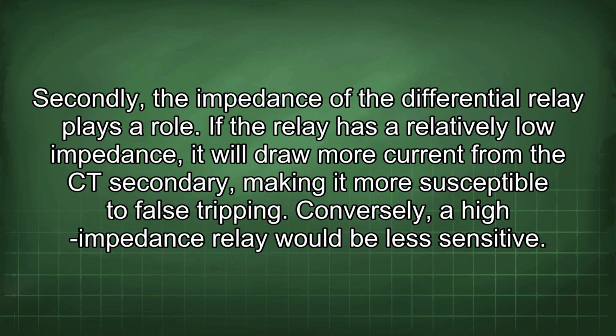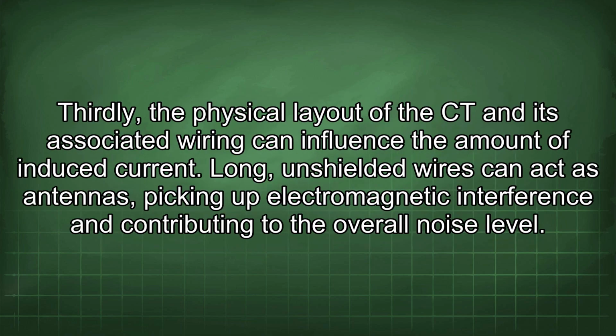This non-linear behavior exacerbates the voltage and current induction in the secondary winding. Secondly, the impedance of the differential relay plays a role. If the relay has a relatively low impedance, it will draw more current from the CT secondary, making it more susceptible to false tripping. Conversely, a high impedance relay would be less sensitive. Thirdly, the physical layout of the CT and its associated wiring can influence the amount of induced current. Long, unshielded wires can act as antennas, picking up electromagnetic interference and contributing to the overall noise level.